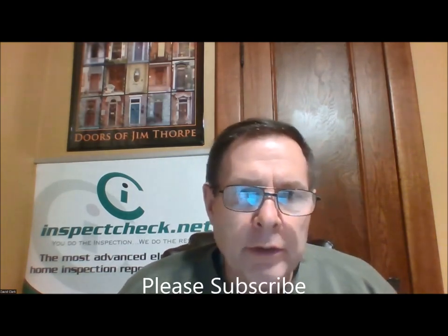So I hope that helped you out. I know a lot of people have questions on them. Again, we're not going to know if they're internally. I mean, we were lucky the one actually was written on there that was common, but we don't necessarily know that we could just tell by the age of that breaker and the age of the service panel and the fact that there's really not too many open slots left, if any, that it may be time for an upgrade. Even though they allow minis and split breakers, I'm not a huge fan of having to put them in because why are we putting them in? Because we need more service.